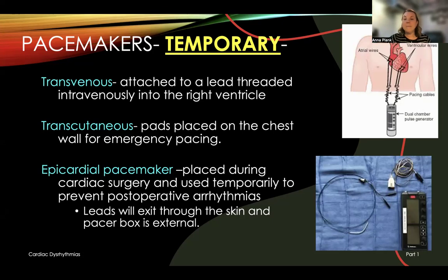There's another one that is an epicardial pacemaker, and this is where these wires have little hooks on the end, right? So if you like crochet, or you've seen those little curvatures at the end. And what these are, during cardiac surgeries, a lot of times they irritate the myocardium, right? So we do open heart surgery, we're in there messing around with the heart, we get it kind of irritated. So because of that irritation, we know that it's more prone to arrhythmias. So what they'll do is they'll leave these little hooked wires right on the end. Okay, and then again, you'll see those wires come out and they'll go right to that little pacing box, and they'll be able to control it.